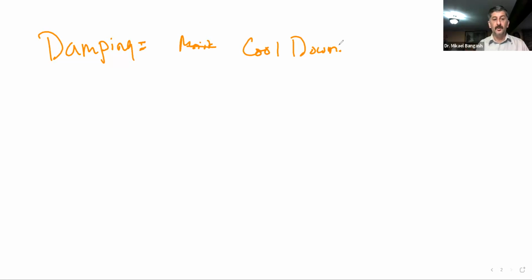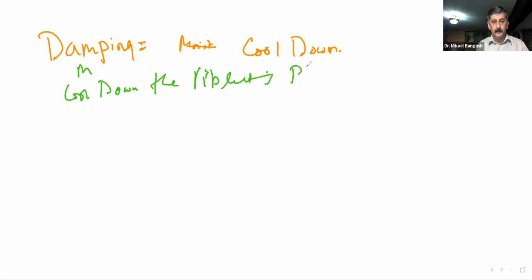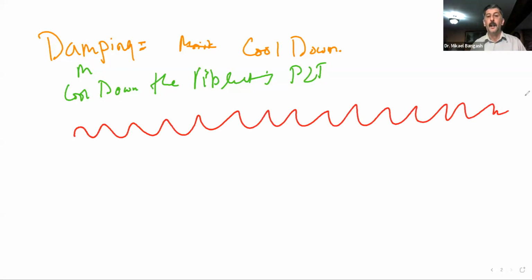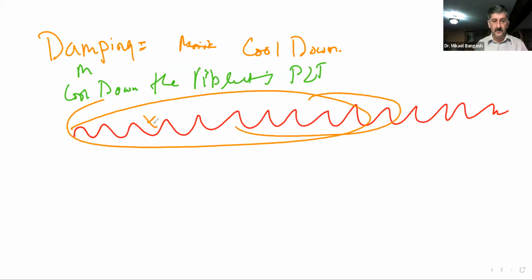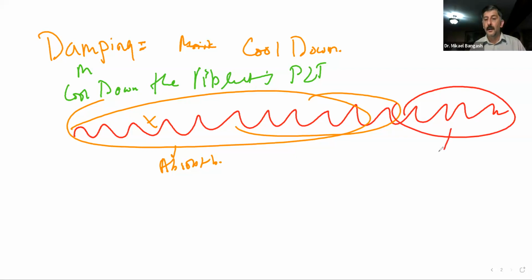So if you have a damping material, it is going to cool down the vibrating PZTs. Without the damping material, we will have a continuous wave. But as a result of the damping material or backing material, what it is going to do is absorb most of this sound energy here. And what are we left with? A pulse.